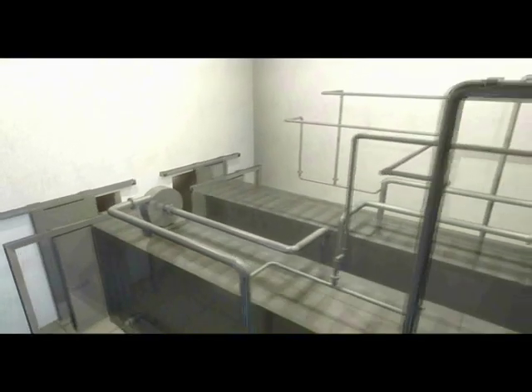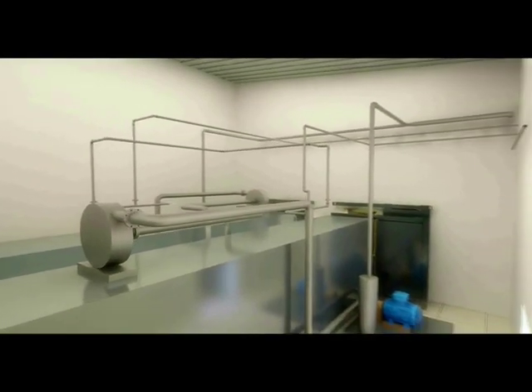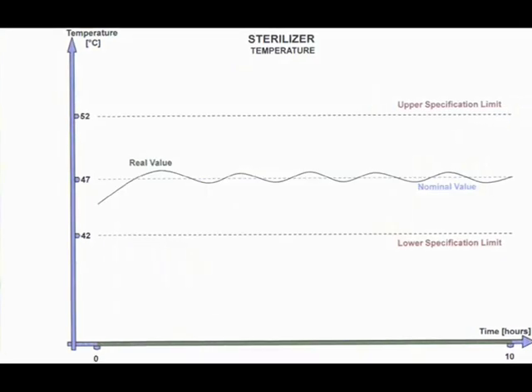The product is transferred automatically by the robot automated transfer system into the sterilizer. After sealing the sterilizer door, air is removed by pulling a vacuum. Leak rate test, nitrogen wash, steam stage.